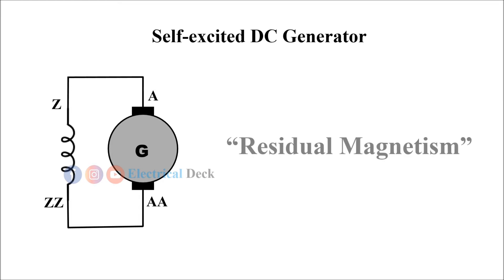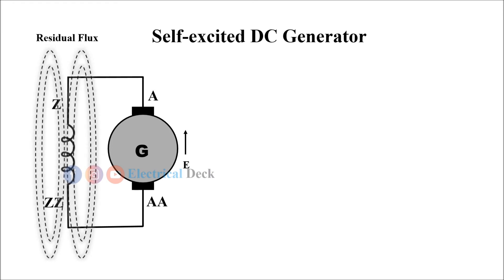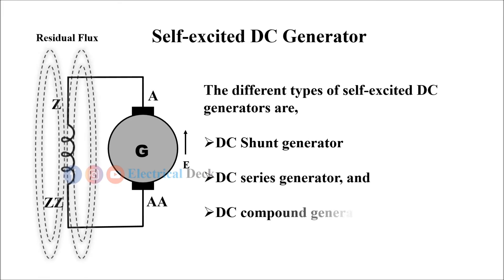The answer is residual magnetism by the field poles. When a generator is started, the field poles possess some residual flux. This flux develops a small EMF in the armature, which in turn drives a small current through the field winding. This further increases the amount of induced EMF in the armature. This process continues till the generator develops the rated voltage at the armature. The different types of self-excited DC generators are DC shunt generator, DC series generator, and DC compound generator.